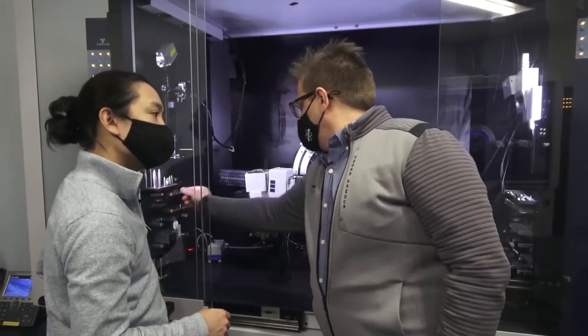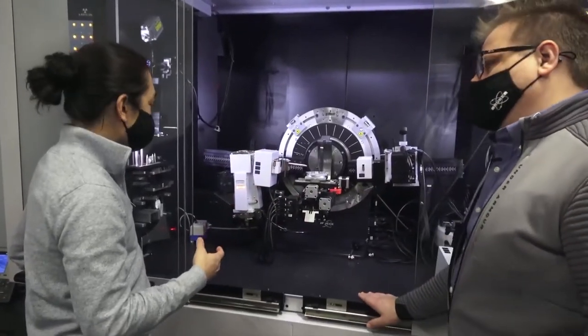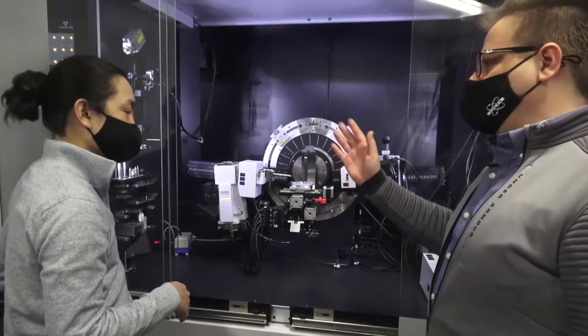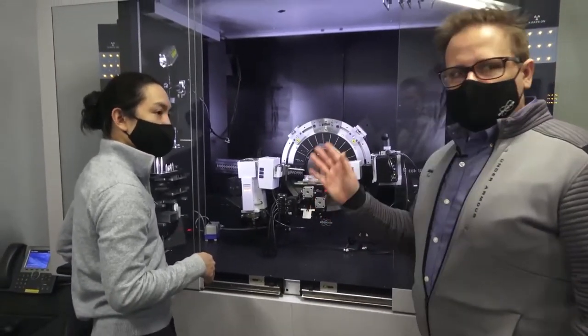It's also easy to change these tubes — a couple of screws, disconnect your water, swap in a new one. So if you're changing from copper to molybdenum or chromium, that tends to be pretty simple.